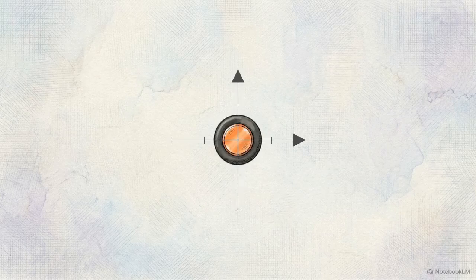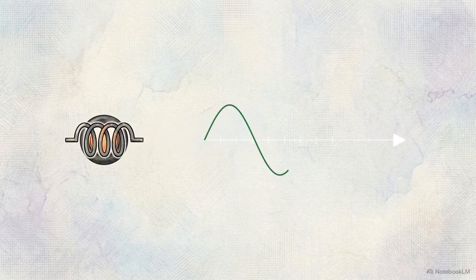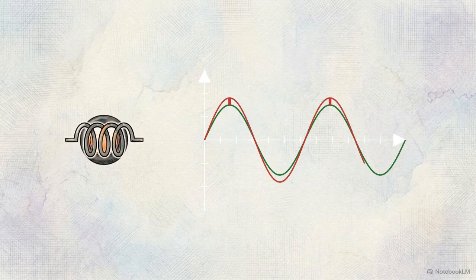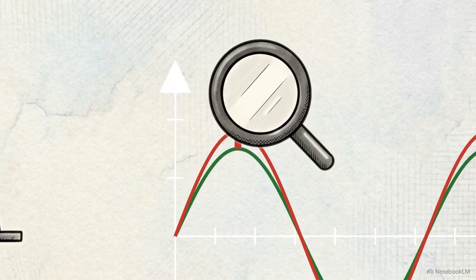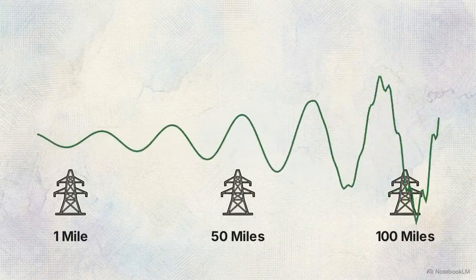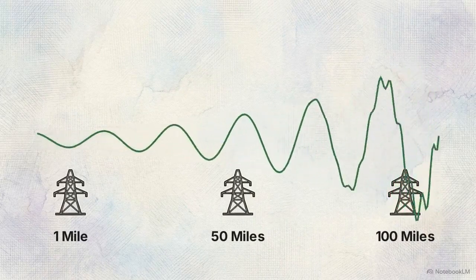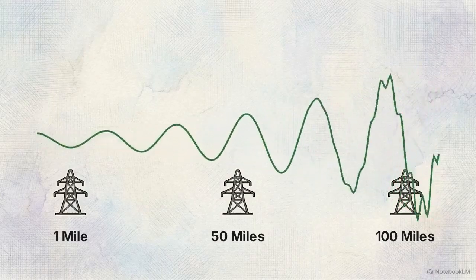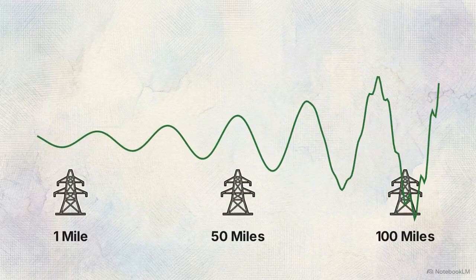Because this charging current is purely capacitive, it leads the voltage by 90 degrees. When this leading current flows through the line's natural magnetic inductance, the phase shift causes the resulting voltage drop to actually stack on top of the system voltage, physically pushing the wave's amplitude upward. At any single point, that interaction creates only a microscopic rise in voltage. But as the charging current travels across the first mile, the 50th mile, and the 100th mile, those localized increases compound. The sine wave swells larger with every passing tower.